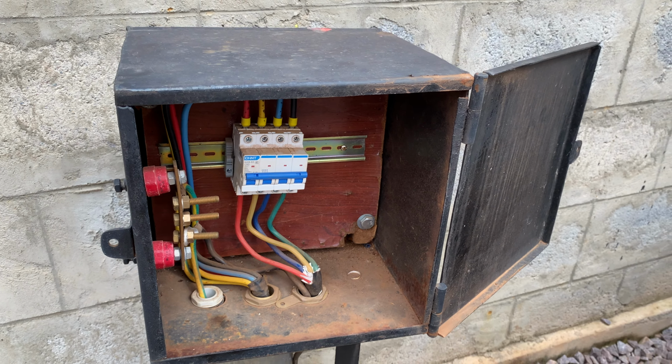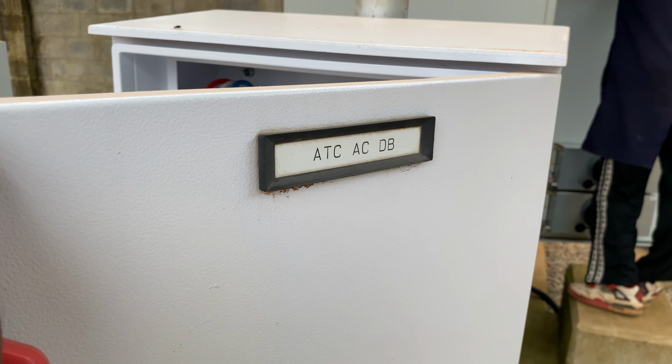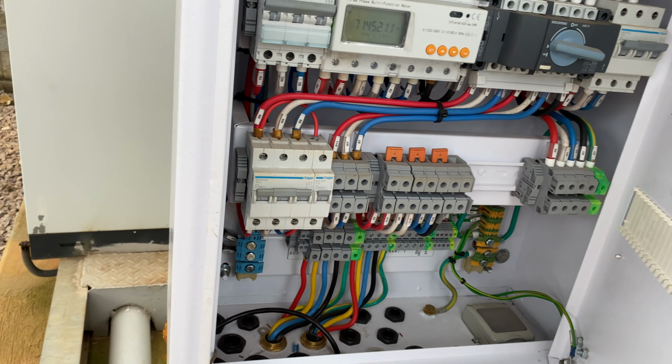In this case they connected it to an automatic changeover, as you see. That means the power from the isolation center plus the power from the generator was connected here to the ATS, and then it flows direct to the SCDB. So from the SCDB, as you see, power from the ATS.